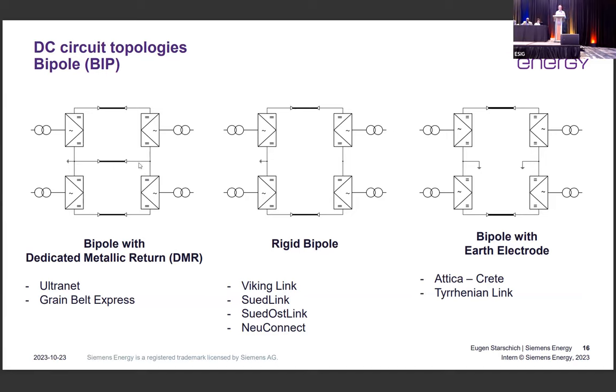So the idea was born to replace it with an earth electrode. That means we don't build a third conductor, but install earth electrodes, and if this conductor is needed, we transmit the power through the earth. There are VSC converters being built that can utilize this technology, like Attica Crete and the Tyrrhenian Link, now under construction. You have more or less the same functionality as the dedicated metallic return, but you save the third conductor, so you save significant costs in the transmission line. The big disadvantage of the earth electrode is environmental issues, which might not allow its construction, but it is still happening.